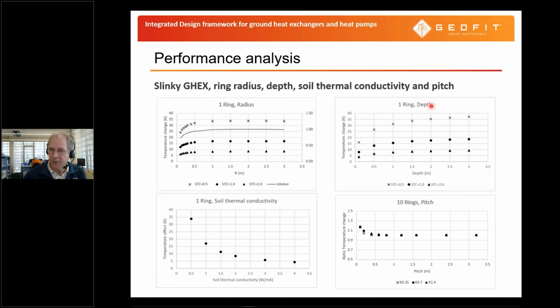Other things that we can look at is ring depth, and here you can see that the deeper the rings, the smaller the effect. So here also we can say we need a kind of minimum depth at which we want to install the ring, because at shallower depths we get both a bigger effect of the analytical solution using mirror sources, which is at very shallow depths not what we would like to have, but also the shallower you go, the more effect there is of seasonal temperature changes on the surface.